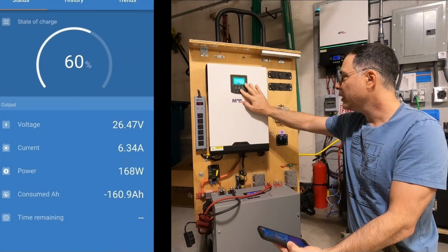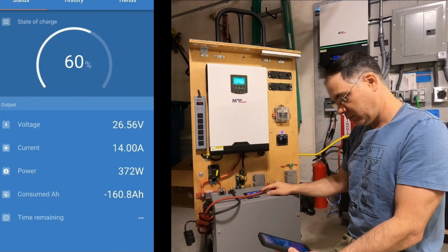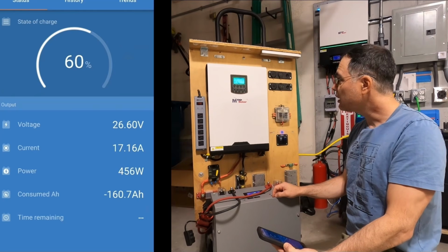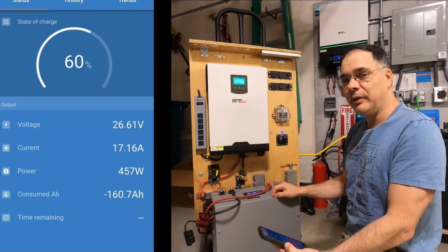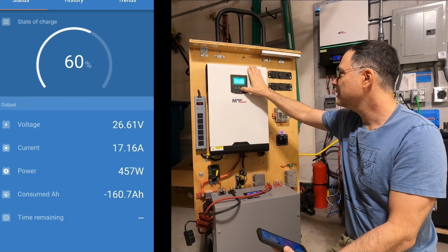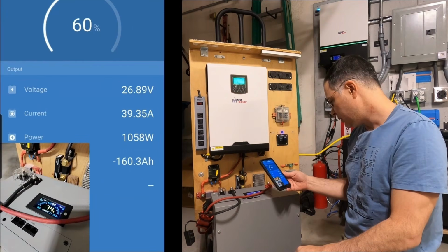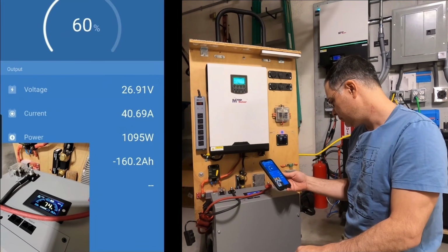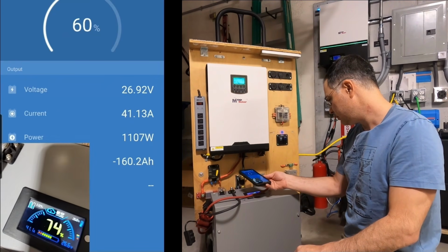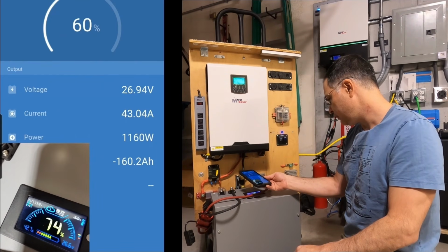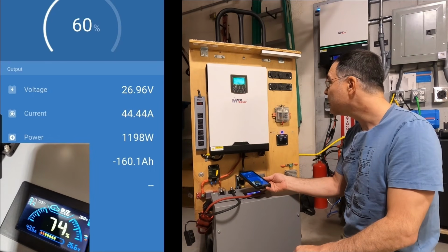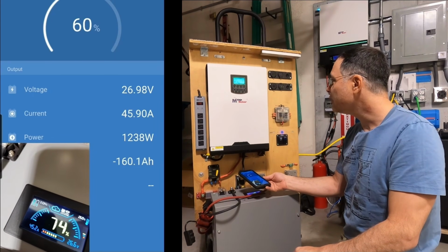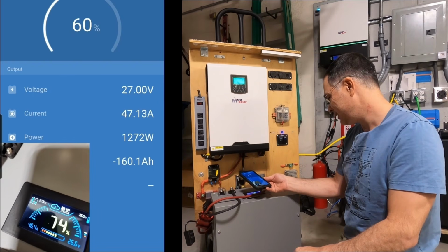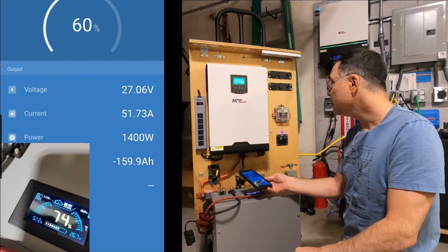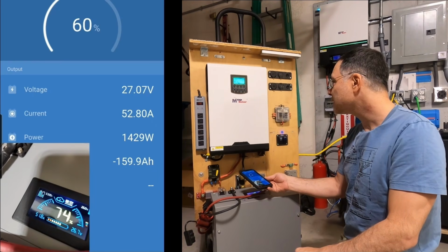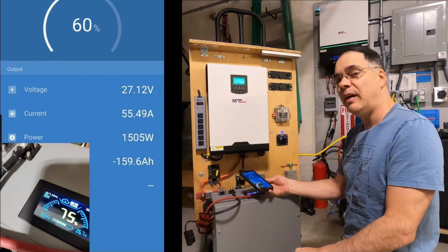I think it's configured for 20 amps. Okay, there's 20 amps, it's not much. Let's kick it up a notch. 40, 50, 60 amps, we're almost to 40 amps. Shunt says 43 and the display says 43. Inverter says 50 already. 58 on the inverter, 60. About a 5 amp discrepancy right there.